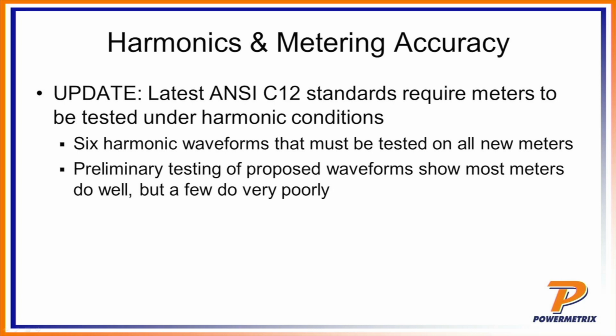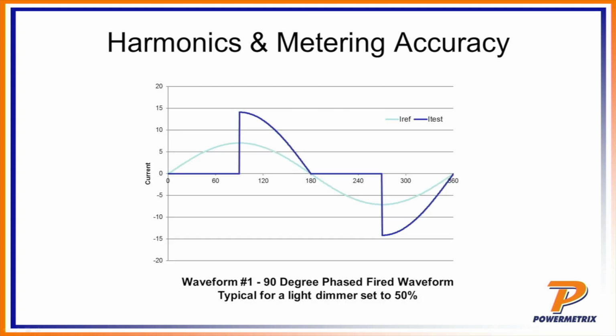That's an issue that has been addressed by ANSI and by the meter manufacturers. The good news is a lot of modern meters will meter harmonic loads without any problem. But ANSI took the extra step of adding those 6 waveforms to the type test so that each and every meter has to be qualified to that. We're going to look at each one of these, and we're going to have a demo in just a minute to show you how our equipment can generate these waveforms and how that affects the metering accuracy.